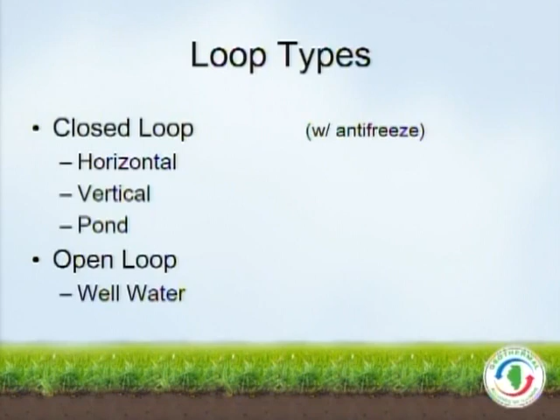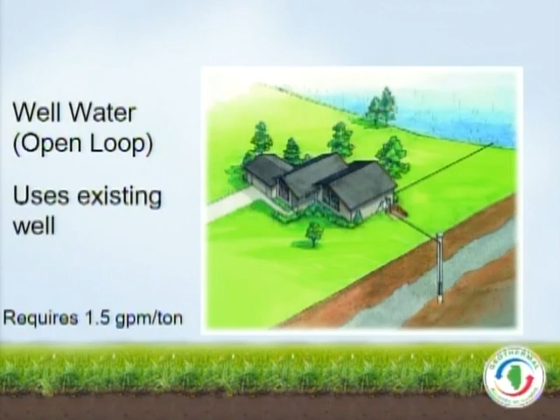These are rare, where you'll see water well open loops. There are a few around here, a couple that I know of, and a few here and there. Where these are really common is in river towns. Rockford has a ton of these applications, right downtown, where you put in a couple of large wells. The water table is just a few feet underground, so you hit water and put in a large well, take water out of the ground, take the heat out of it, or inject the heat into it in the summer, then inject it into the river, which is perfectly fine. You're not doing anything to that water except adding about 6 degrees in the summer and taking about 6 degrees out in the winter. You don't see too many of these, it's pretty much just in river towns.